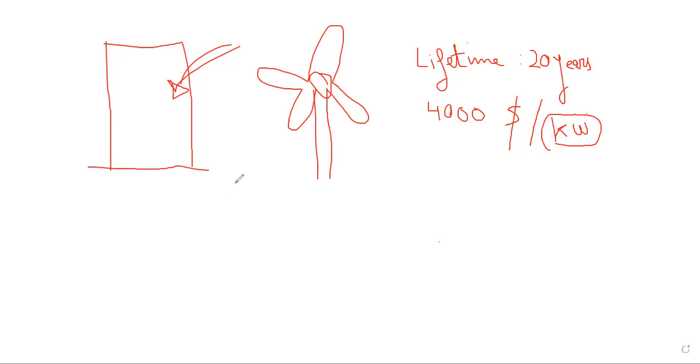So first you ask the manufacturer what is the number of hours of operation per day of this turbine? In general you need to have some time to shut off your turbine, because if it is always under continuous operation, this will increase the maintenance cost and reduce its lifetime. So maybe they can tell you it's recommended to operate it between 10 and 18 hours per day.